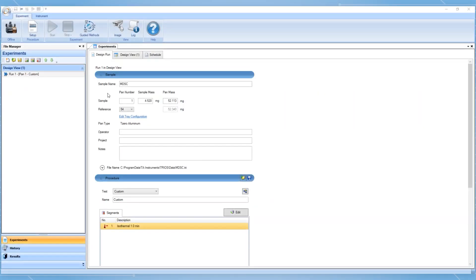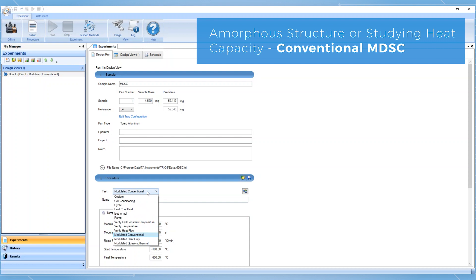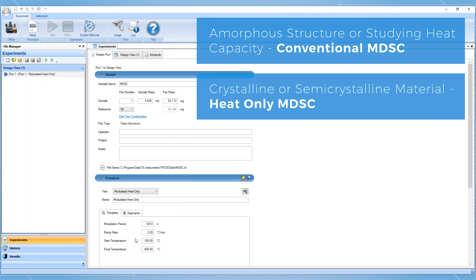Remember that finding the appropriate MDSC conditions can be an iterative process, and one method might not fit all materials. Conventional MDSC is typically used when studying amorphous structures or heat capacity, and heat-only conditions should be used for crystalline and semi-crystalline materials. A good place to start when selecting parameters for a new material is with an average heating rate of two degrees per minute, a temperature amplitude of plus or minus one degree Celsius, over a period of 60 seconds when analyzing transitions, or 120 seconds when studying heat capacity.